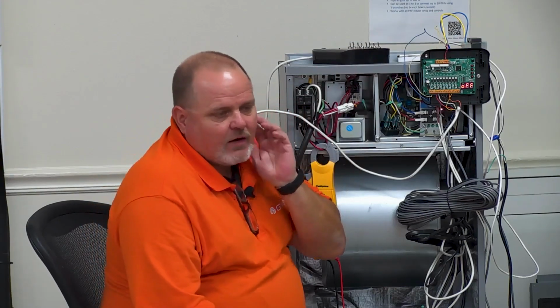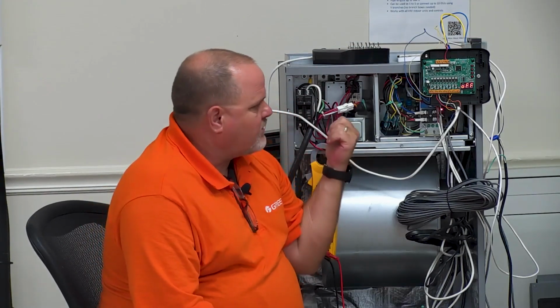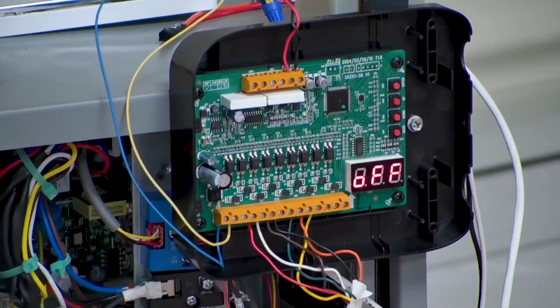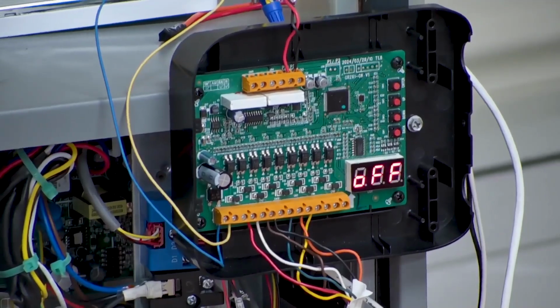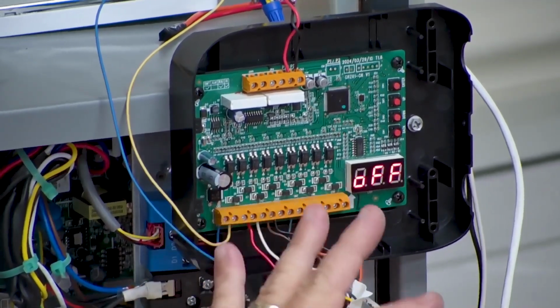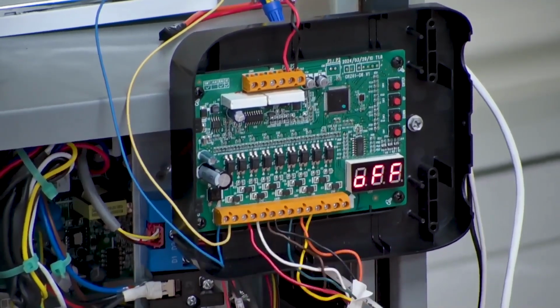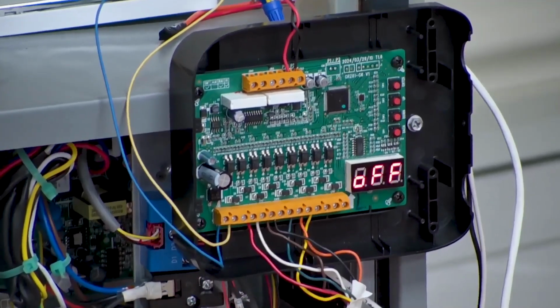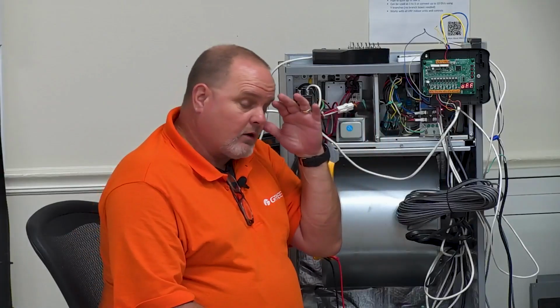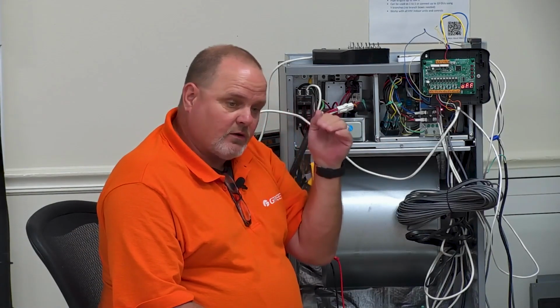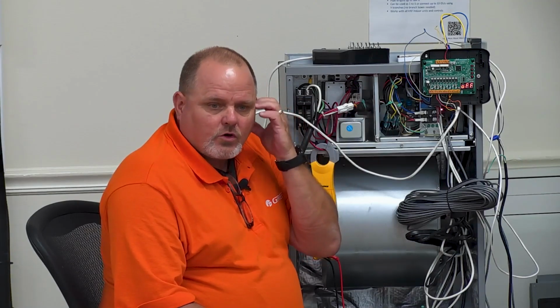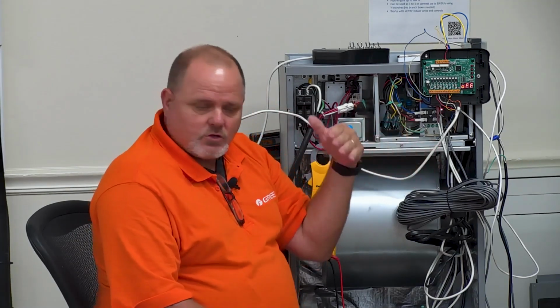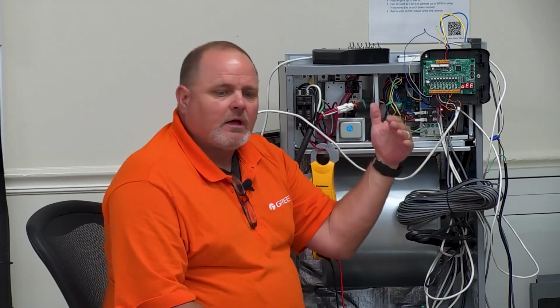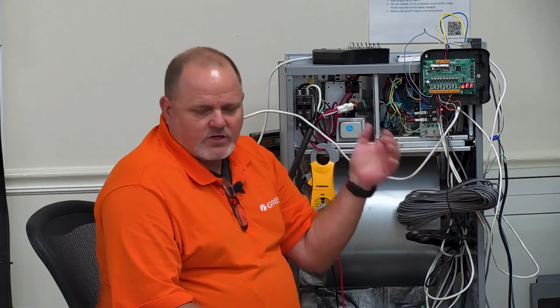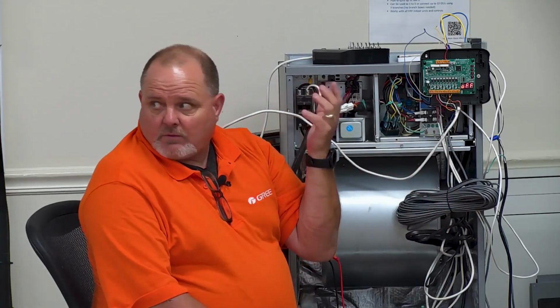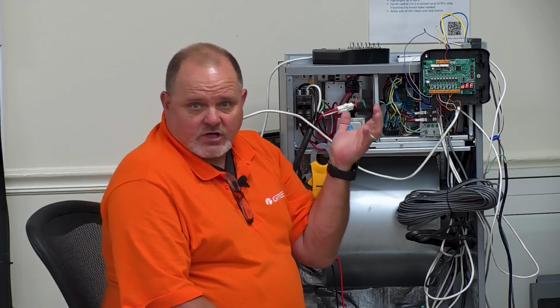So now, if electric heat comes on, something I noticed with this, if you get electric heat on, it's got its own blower off time that has nothing to do with this P code setting. The P03 is more like a heat pump setting, how long it stays on after you lose the call, for heat pump cooling mode. So heating mode or cooling mode of the heat pump, you can set those delays and they'll actually run that thing anywhere from 5 to 20 minutes in your different settings.